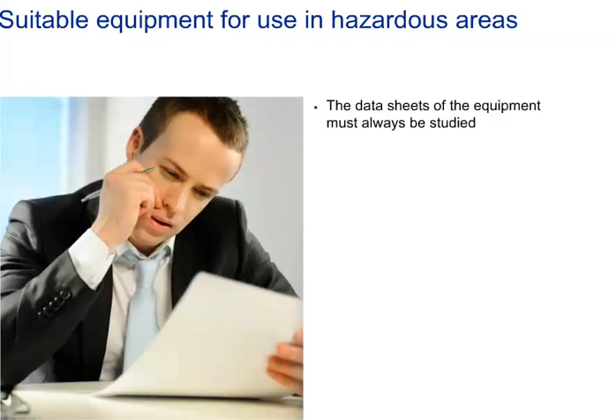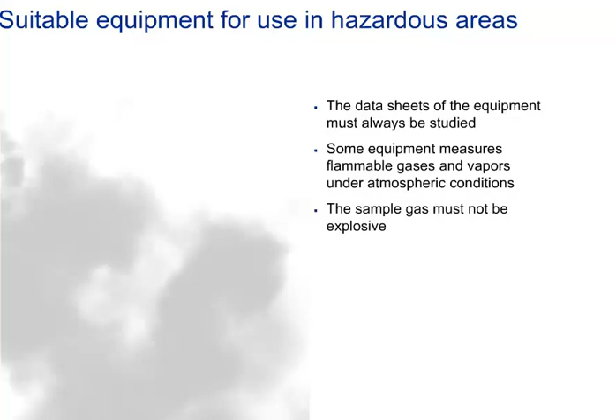As a rule, some equipment, such as gas analyzers, can measure flammable gases and vapors under atmospheric conditions. The sample gas must not be explosive under normal conditions. If the sample gas is explosive in the event of a sample gas supply failure, then only seldom and briefly, in accordance with the Zone 2 definition. All parameters relevant to explosion protection are based on atmospheric conditions. These conditions are absolute pressure 0.8 to 1.1 bar, temperature -20 to +60 degrees Celsius, oxygen content 21 volume%, relative humidity up to saturation.